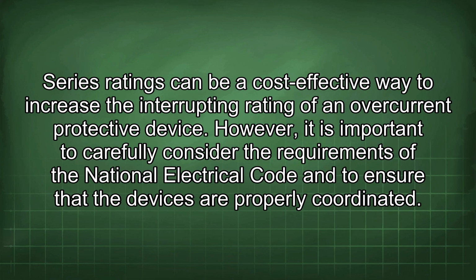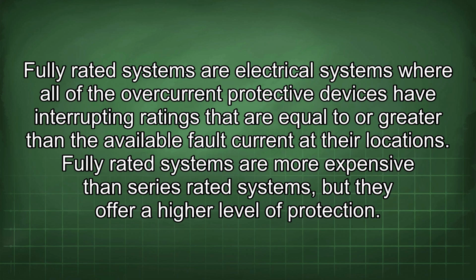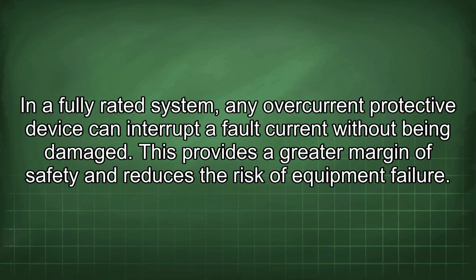Fully rated systems are electrical systems where all of the overcurrent protective devices have interrupting ratings that are equal to or greater than the available fault current at their locations. Fully rated systems are more expensive than series rated systems, but they offer a higher level of protection. In a fully rated system, any overcurrent protective device can interrupt a fault current without being damaged. This provides a greater margin of safety and reduces the risk of equipment failure.